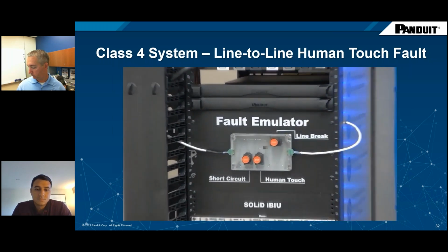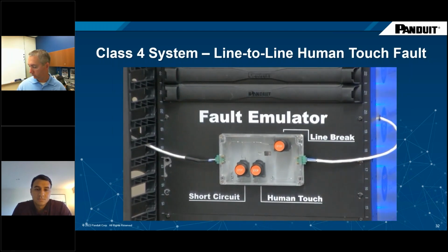This is a fault emulator box that allows us to introduce different faults to the cable delivering pulse current to the converter. The 3 faults presented here are a short circuit, a line break, and a line-to-line human touch. The human touch is represented using a resistor, as if someone is holding both ends of the conductor. Pressing any of those buttons would introduce one of the faults.